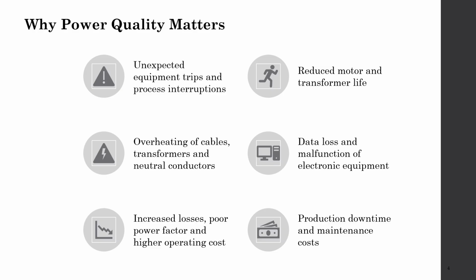Then we talk about why power quality matters. Here, we can go step by step. Unexpected equipment trips and interruption. Reduced motor and transformer life. Overheating of cable, transformers and neutral conductor, data loss and malfunction of electronic equipment, increased losses, lower power factor and higher operating costs, production downtime and maintenance costs.